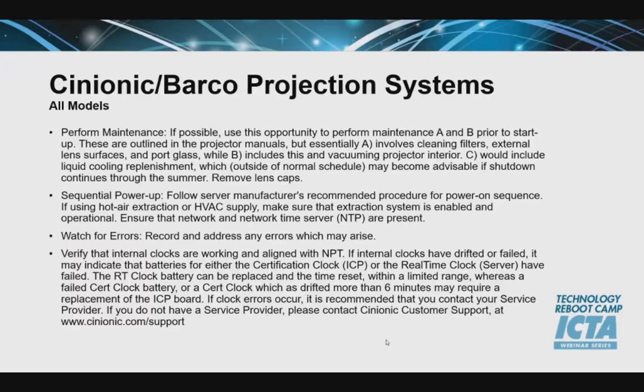One of the things you're going to want to make sure of, throughout doing the sequential power-ups every 7 days or every 3 days, is that your real-time clock and ICP clocks, the NTP time server, are syncing up properly. In some cases, if the time drift gets more than 6 minutes, you might be required to replace an ICP board. So if you notice any errors like that, please reach out to your service provider or the individual manufacturer.